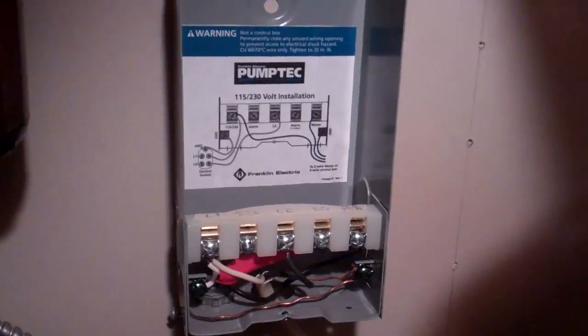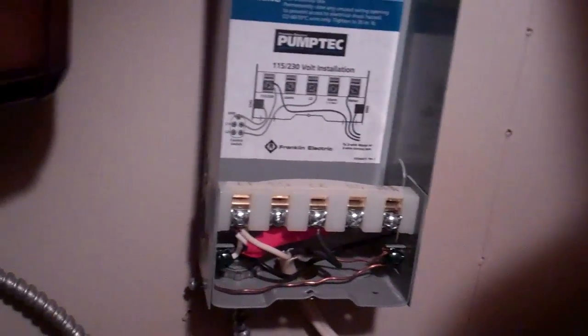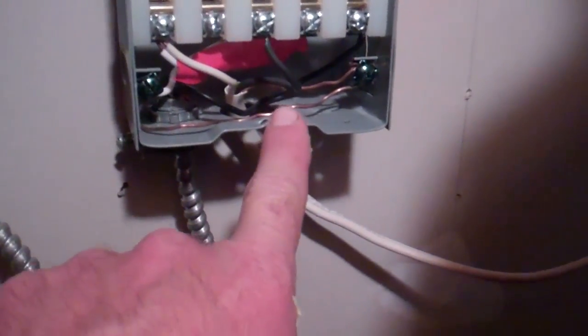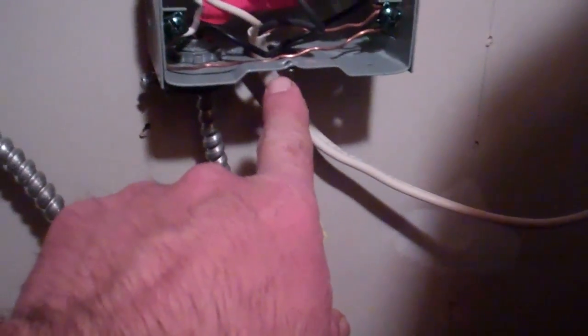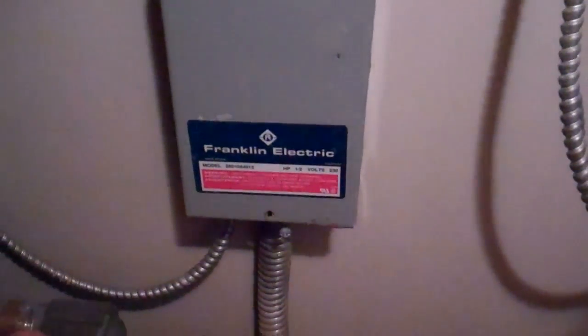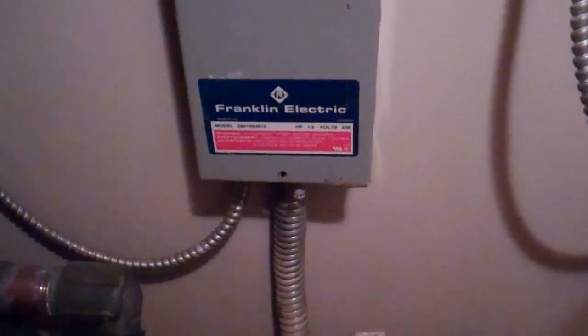Here's what this PumpTec unit looks like with the cover off. I killed the AC power to it just so I don't get a shock in here. But basically, this lead here comes over to the AC power, and the unit itself will switch the power out to this line here which goes to the pump down in the well, the submersible pump.